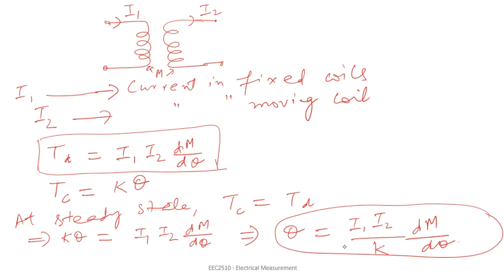As in the case of the PMMC type instrument, the deflecting torque of the electrodynamometer type instrument is dependent on the field flux, the coil current, the coil dimension, and the number of coil turns. However, the field flux is directly proportional to the current through the field coils in this case, and the moving coil flux is directly proportional to the current through the moving coil.